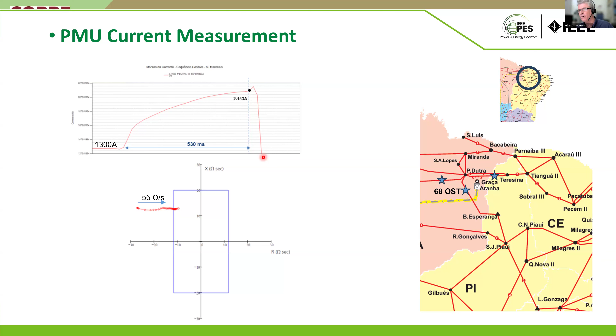There are 3 lines, but I'm showing the current of only this line. So the 68 out-of-step tripping tripped these 3 lines, half a second of the problem. Then the system was already deteriorated, and with this line, then a lot of problems, a cascading of failures. I will not show you the whole thing, but then the thing tripped.